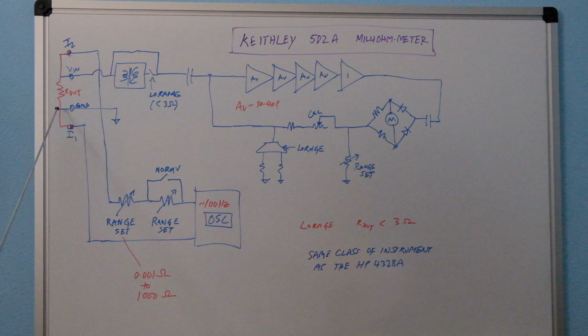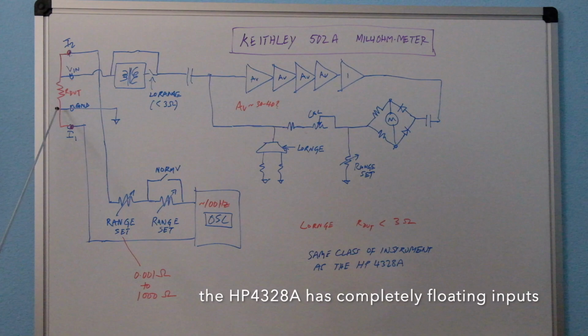Now one disadvantage of this machine compared to this guy is that the voltage node here, the return path, is actually grounded. So this machine can measure resistances in the presence of DC voltages when it's in circuit, because it's actually using an AC signal to measure the response. Basically it's a tuned amplifier over here, and the frequency of this is around 100 Hertz, so anything that is outside this range will be attenuated severely, and it can actually handle several hundred volts. This instrument, however, has both floating voltage and current terminals, so it doesn't suffer from that problem.